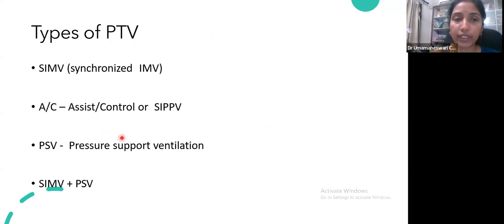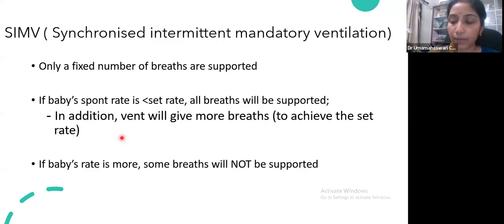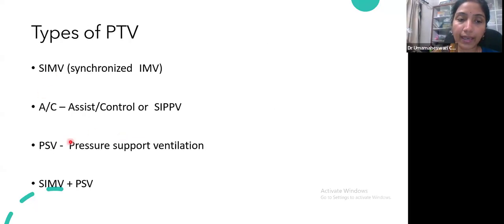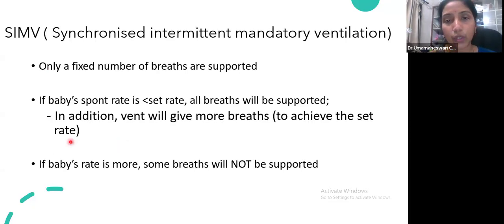So depending on the patient trigger ventilation, you have SIMV, which is synchronized intermittent mandatory ventilation, assist control or SIPPV, which is synchronized intermittent positive pressure ventilation, and PSV, which is pressure support ventilation. Sometimes you can combine SIMV with PSV. So what is SIMV? Very simply, you have a set respiratory rate from the ventilator. The ventilator supports only the set rate. However, it allows the baby to take breaths in between, so it does not prevent the baby from breathing. If the baby wants to take some breaths over and above whatever has been set as the respiratory rate, it allows it, but only the set breath rate is supported by the ventilator. So if the baby is breathing more, some of the breaths will go unsupported.